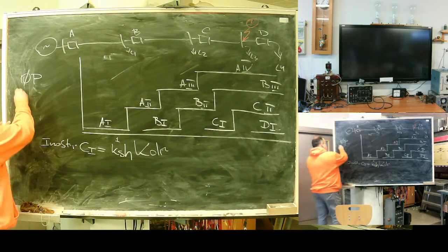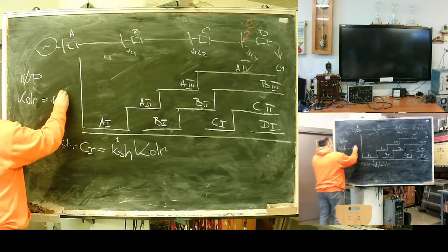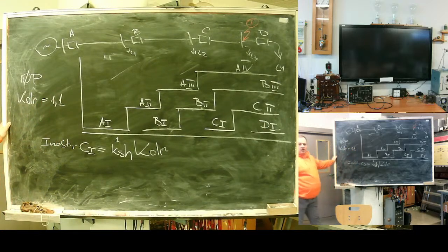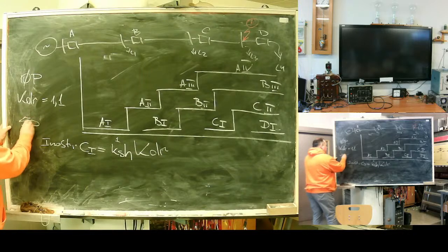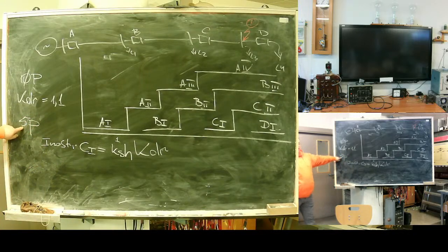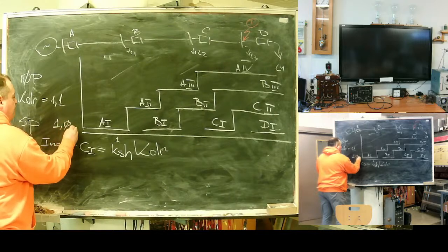For this case, the safety factor is 1.1. If your company is rich enough and bought you 5P, 5P for protection, do not use a metering transformer. Use 5P.